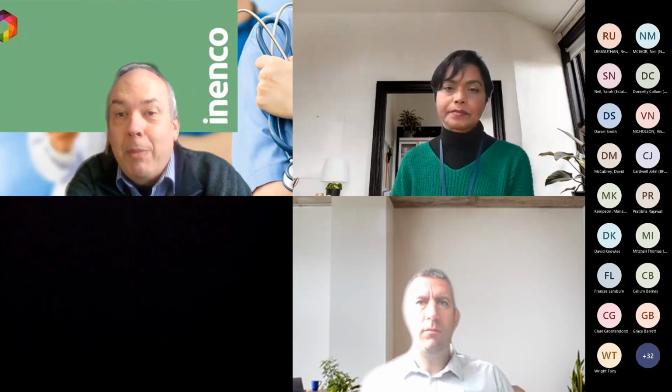Thanks. Right, at Inenco we don't get involved in things like geology. That's not our specialist subject. But what's very interesting with underground heat pumps, and it's similar to mine heat pumps, is that in London there are 2 projects where they have air source heat pumps located in old abandoned tube stations. The tube stations are typically about 20 Celsius, summer and winter. So they pick up energy from the tube stations, which would otherwise be expelled to atmosphere, and they operate at higher temperatures and are therefore more efficient. Funnily enough, they are air source heat pumps, but they operate as if they were ground source heat pumps underground.